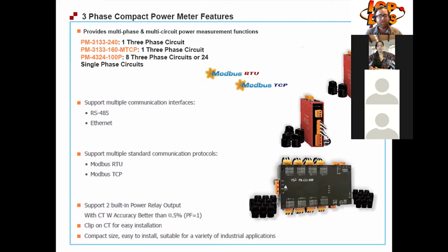They can be applied to low, medium, and high voltage circuits to measure the EM field from a power line and convert that data into machine-readable power readings, into true RMS power measurements, kilowatt-hours, apparent power, etc. They communicate over Modbus RTU and Modbus TCP. In these examples, we also have CAN-open modules available, but we're just talking about the most popular ones today.